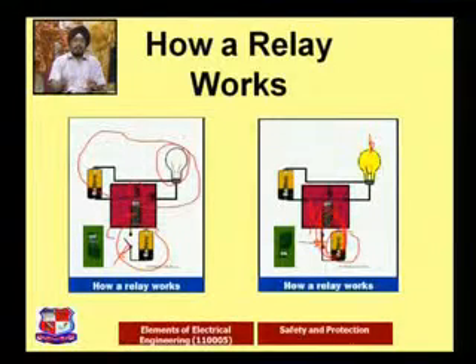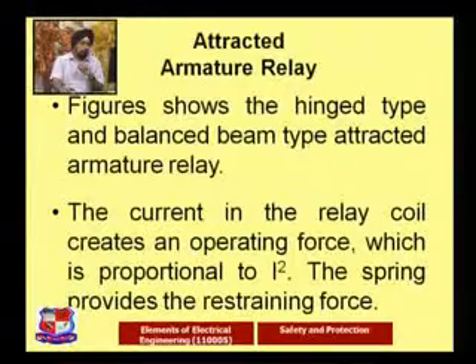In an actual case, things are reversed. In the normal condition, this bulb or circuit is in the on condition. When the relay trips and the trip signals are there, it comes into the open condition. So there are two types of contacts we deal with, NC and NO, normally closed and normally open. This is just an animation which shows how the relay works. The types of relays are different, but the fundamental working principle always remains the same. There is no change in that.